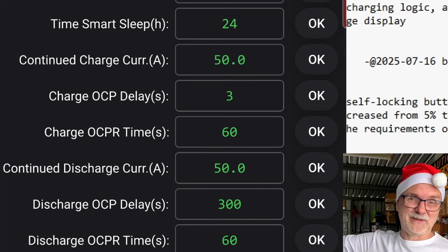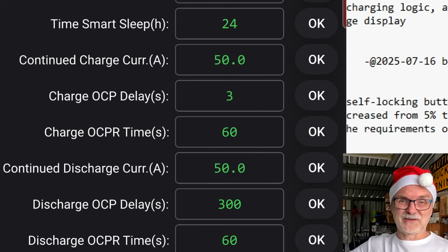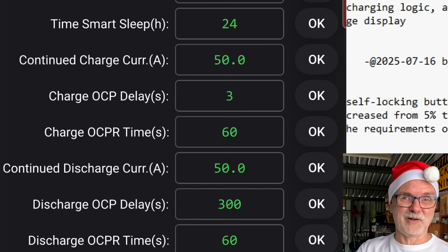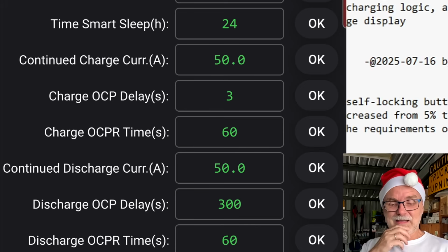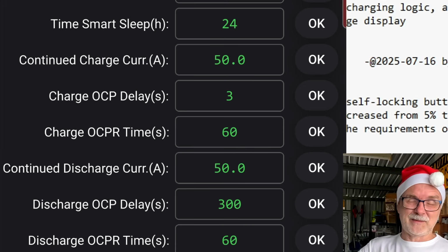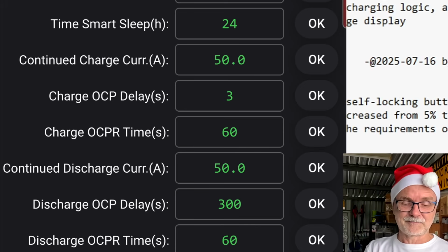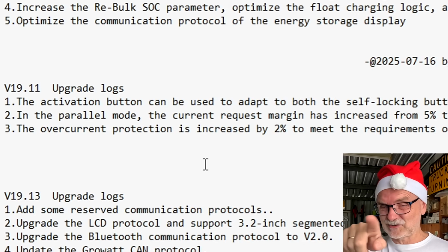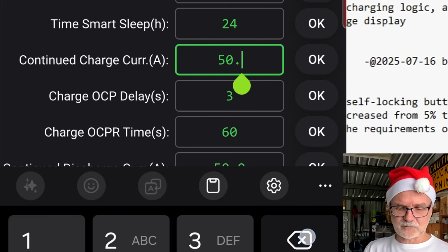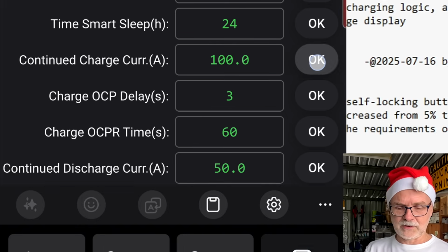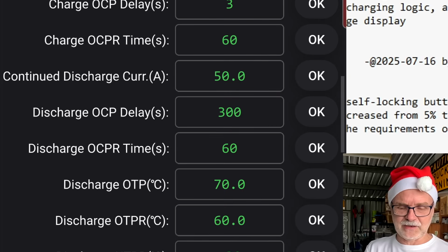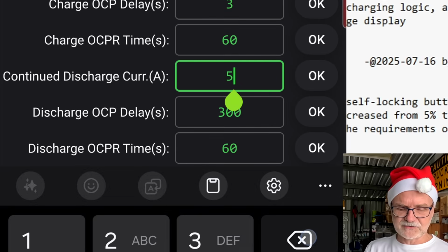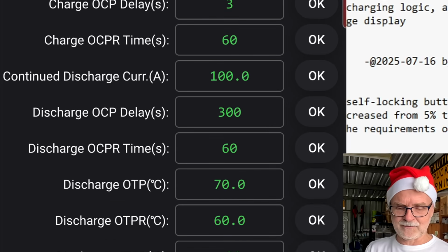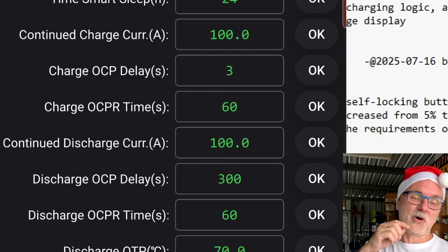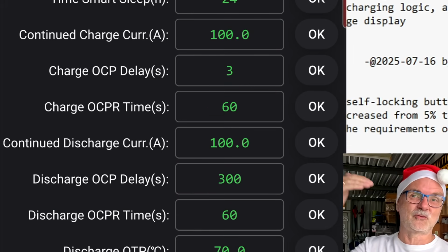In fact, I've set all my BMSs to 50 amps of charge and discharge current here, because this is all monitored and set by the iBMS system. So I'm not using these parameters anymore. But at the moment, I have connected the master BMS to the Cerbo GX just to demonstrate what this actually means here, and set this one here to 100 amps, 100%, yeah, it's easier to calculate. And the same here for the discharge current, we set this one to 100 amps as well. So the BMS would actually now report these 100 amps charging and discharging to your inverter, yeah?